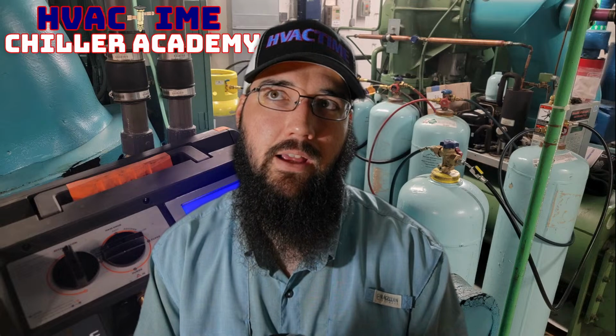With constant speed, that motor doesn't change. That's the whole point behind the constant speed. But there's still the fact that the impeller is spinning, so we have a specific amount of heat from friction constantly being generated. Because we can't slow the compressor down, we can't reduce the amount of heat that the impeller is generating just from rotation on its own. So what ends up happening is, as we unload the machine and move less refrigerant into the impeller, keep in mind, these are suction cooled compressors. There are some that use some liquid injection, but for the most part the majority of these are going to be suction cooled. Of course, then we could get into Turbocor, and I could get off on a tangent there.